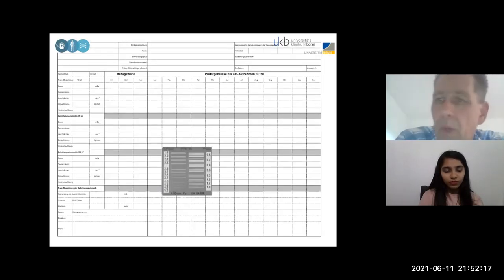Now we come to something where we do it kV related. So we have certain kV steps. That is something you have to agree on in the acceptance test. We agreed on 70 kV and 102. It's funny, 102? No, it's not funny. This vendor could not give 100 kV; he could only give 102. So you should do your acceptance at 102. Then you measure the dose, the luminescence, and the resolution. On the left-hand side is with automatic exposure control, and the other one is manual. So you set everything manually, and you don't use the automatic exposure control. And that is what we also do monthly.